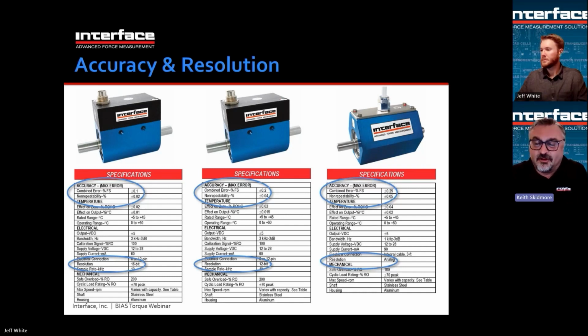The limit of your resolution, though, is going to be noise. You have 24 bits, millions and millions of counts of resolution, but if a lot of that resolution is noise, it is not usable. So keep that in mind too. The limiting factor a lot of the time is noise, not the actual electrical resolution of the sensor. Noise can be mechanical, can be induced by motor drives into the measurement system, or into the torque sensor. Analog output noise can also be induced into the device that's being used to measure it. It can be grounding, or noise due to variable frequency drives. So a lot of times there can be a significant amount of signal noise in a torque system that limits the resolution. Moving on.